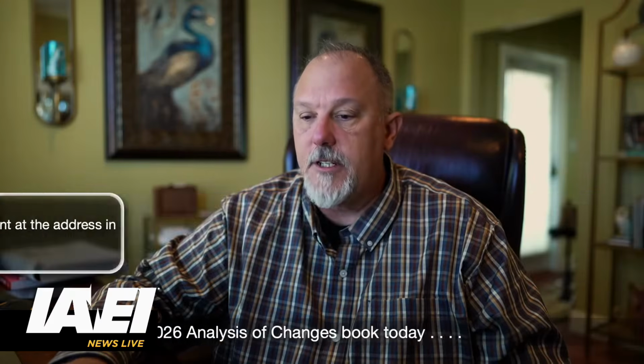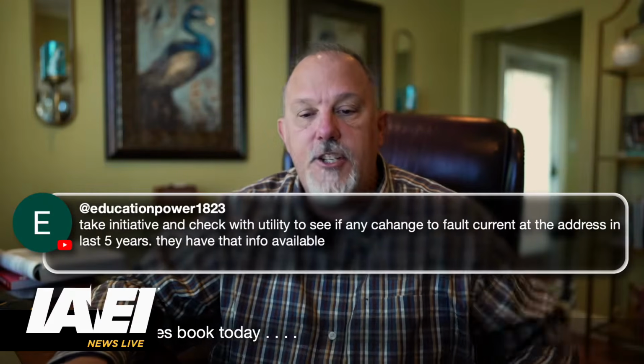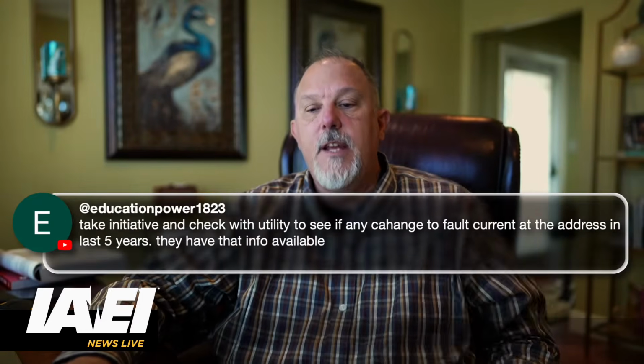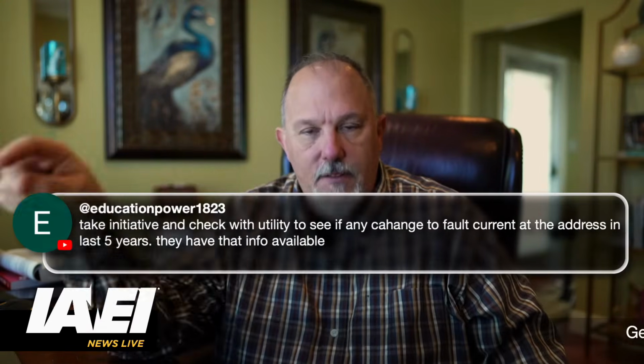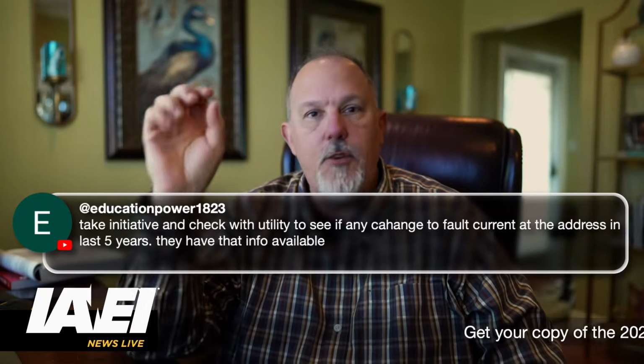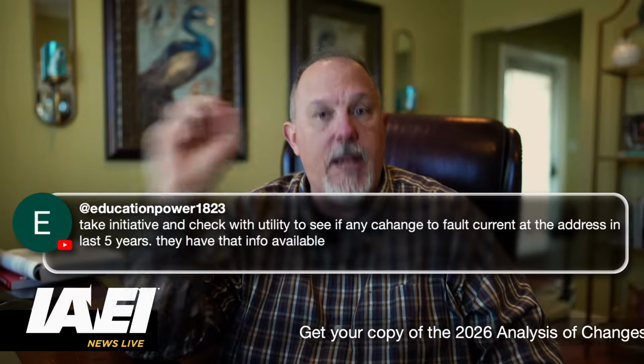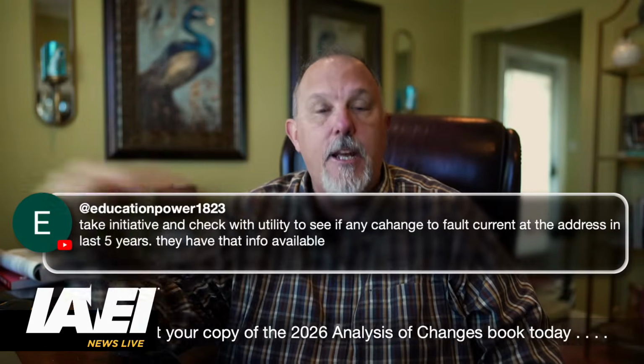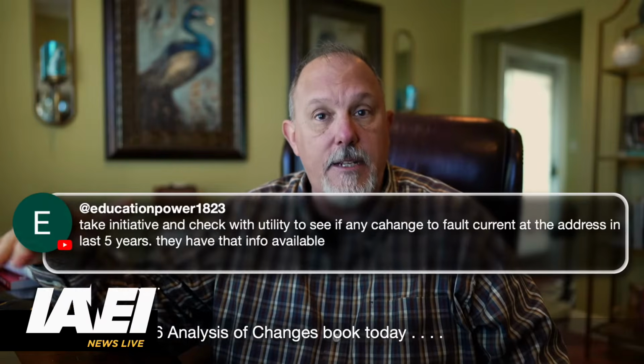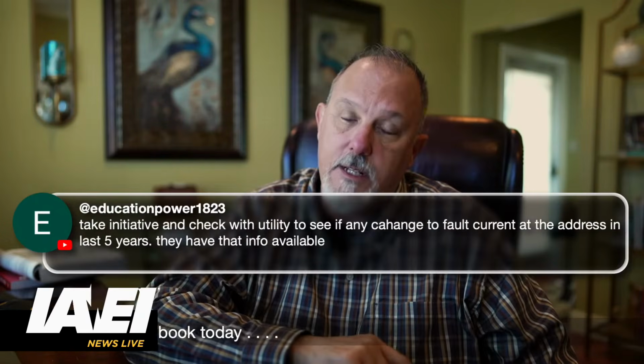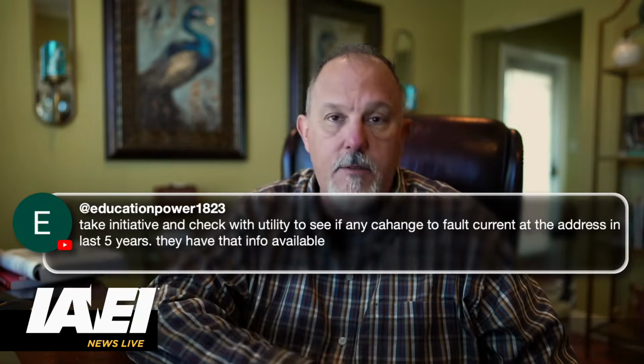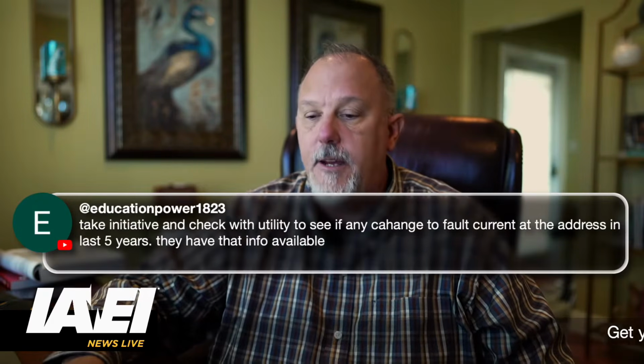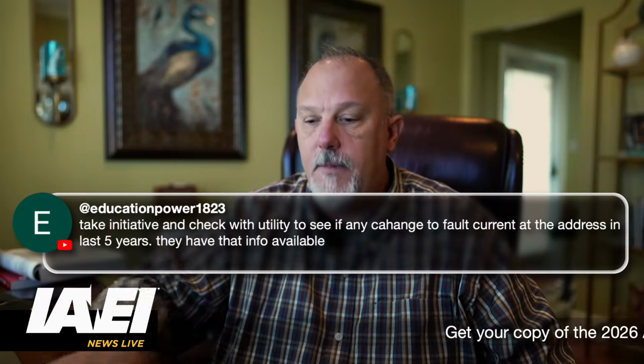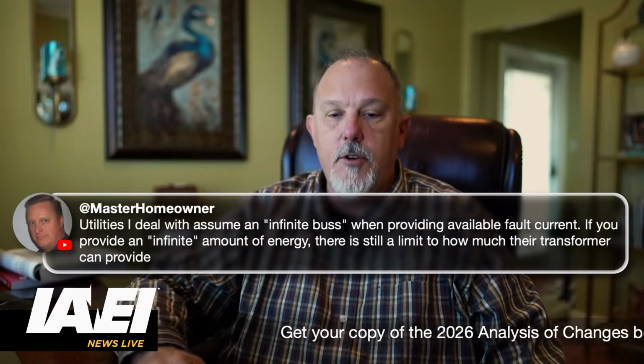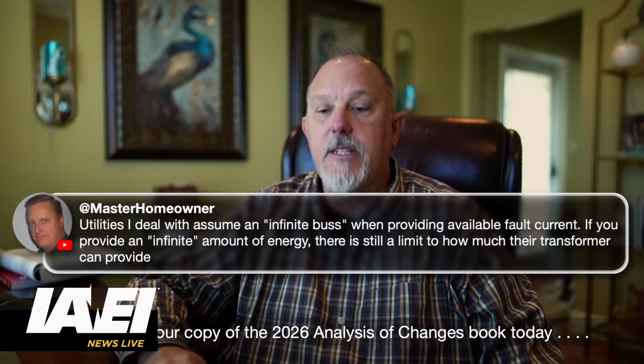I get you, Robert. Take initiative and check with the utility to see if any changes. That's part of the 5-year review, and when you add motors, or if you're going to make modifications in the plant and update your studies, always check with the utility. Double check with the utility, get updated numbers from them at that point as well. Master homeowner, utilities I deal with assume an infinite bus.